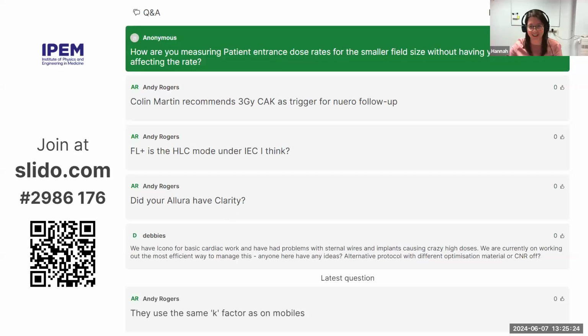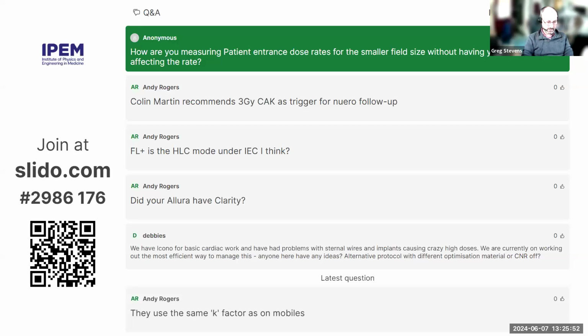A continual challenge, maybe. The major issue is that at the moment we're using a needle. What do they call them? The transparent detector from the Unfors Xi. This little transparent detector is perfect because it's about 0.5 centimeter by about 4 or 5 millimeters, so even with the magnification, you're still within that parameter, and you can keep out of the active area.